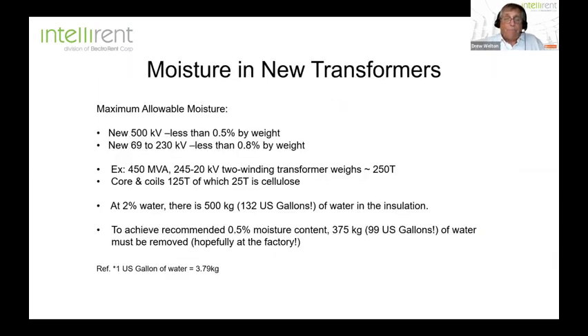Okay, so in a brand new transformer, and I mentioned this earlier, based on their size, brand new transformers have to have no more than 0.5% or 0.8% moisture by weight. If we were to check the moisture in the insulating system on a new transformer, let's say a fairly sizable transformer, in this case 450 MVA, at 2% water, we would have to extract almost 99 gallons out of the transformer itself in order for it to meet the industry standard for a new transformer. A lot of people don't think about this.